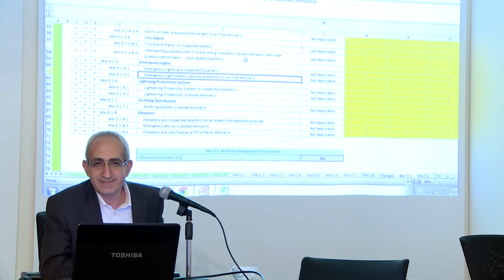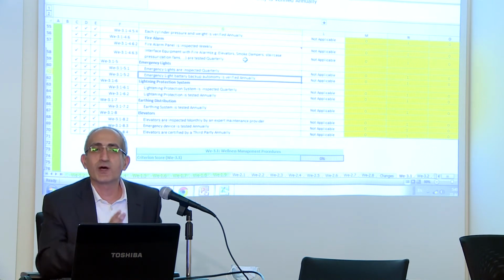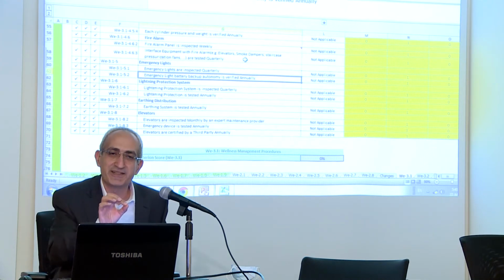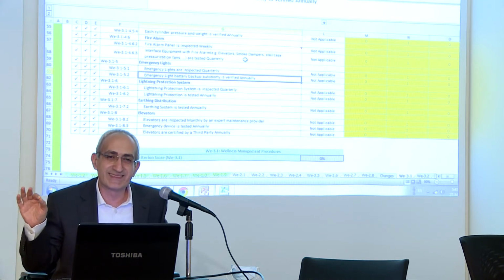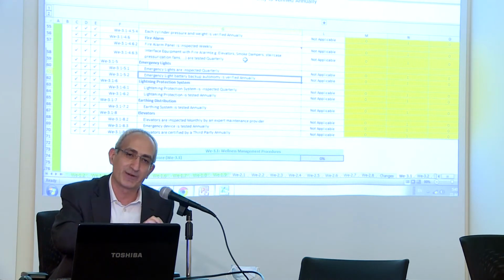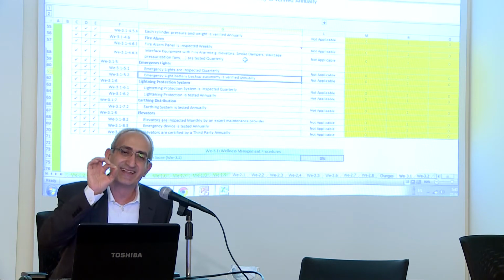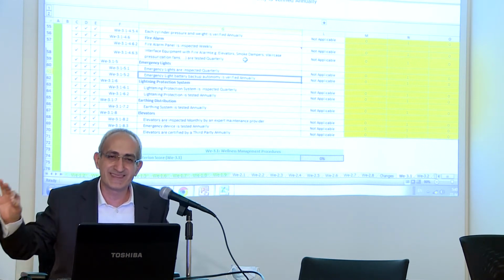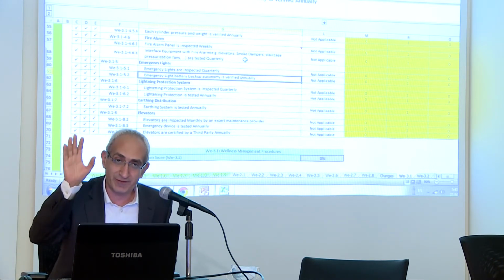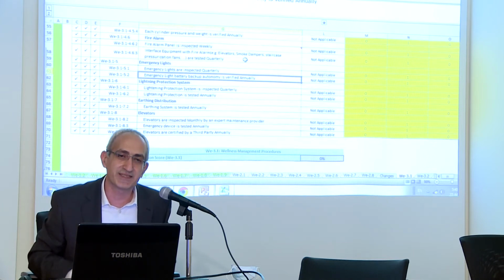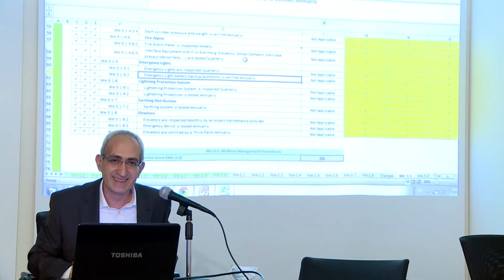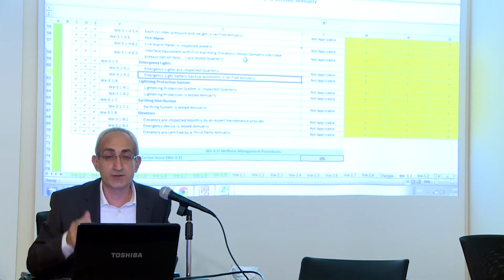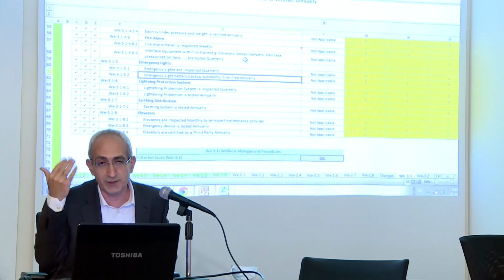We are in Lebanon, so we have to adapt ourselves here. If you are in Beirut, it needs to be autonomy of 3 hours. That's why the design is related. So design was addressing the owner project requirements in the commissioning phase. Owner project requirements dictated 4 hours or 5 hours. We need to ensure that this is being maintained through the life of the building. Especially now we are dealing with lead, so lead could last longer. But you can reduce the battery storage. Yes.